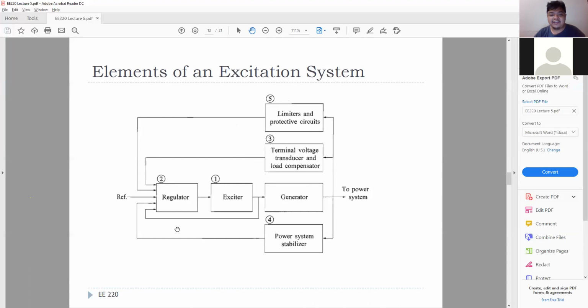The generator has to operate at its own voltage level. If it's operating at that voltage level, depending on its MVAR capability, it will initiate its exciter to eventually emit some MVARs. There's a feedback mechanism, the power system stabilizer, if it needs further MVARs as instructed by the power system or the power system operator.